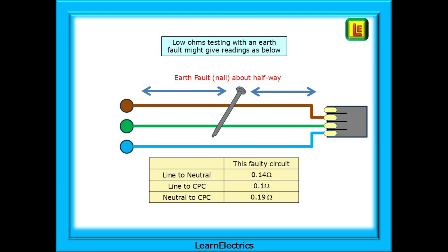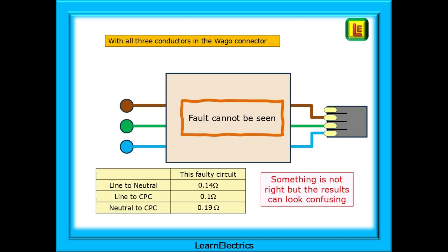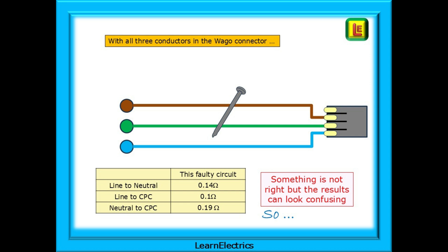Because it involves the earth conductor we call this an earth fault — or at least we should do in assessments and exams. What readings would a low ohms test on this circuit show? As you can see from the table, the readings are nothing like those for the good circuit and they don't appear to make sense. But if you didn't know what the fault was or where it was, how would we go about finding it? If we low ohms resistance test the circuit it's obvious that something is not right, but the results can look confusing. Part of this is because we still have all three conductors linked together in the Wago — we need to take a step back and find some clarity.